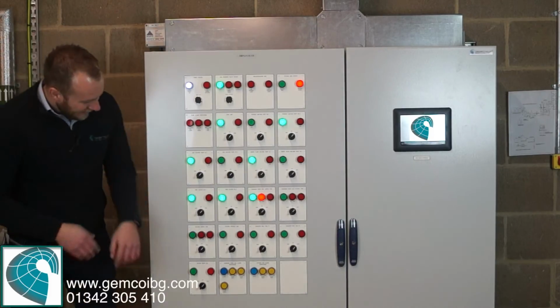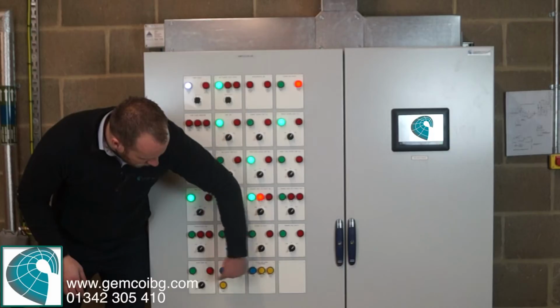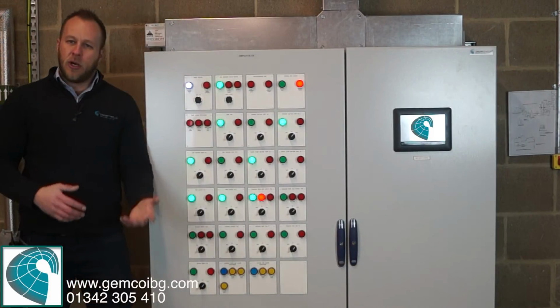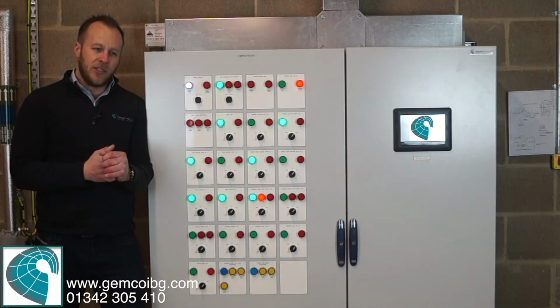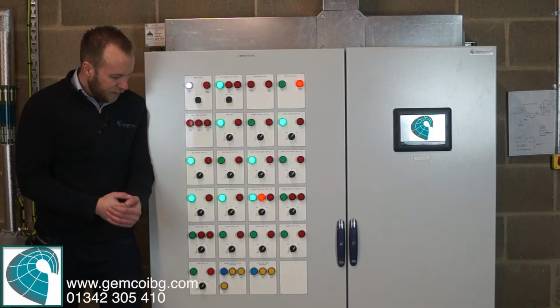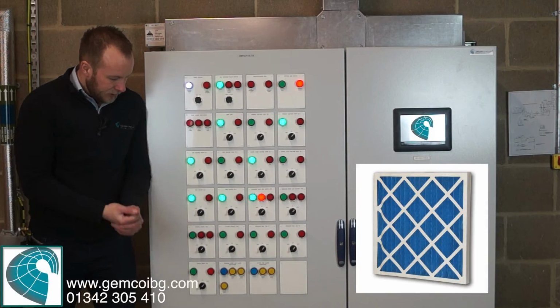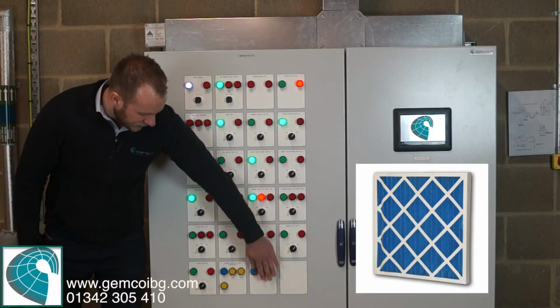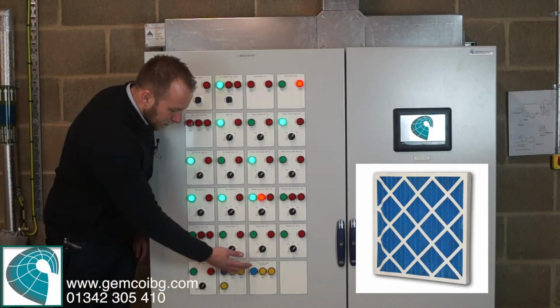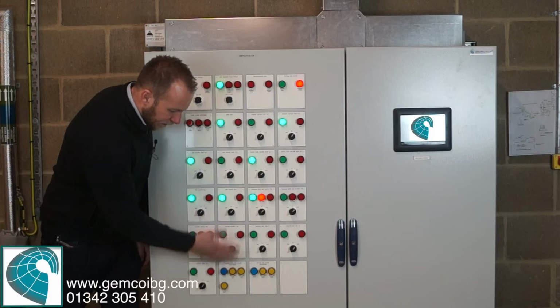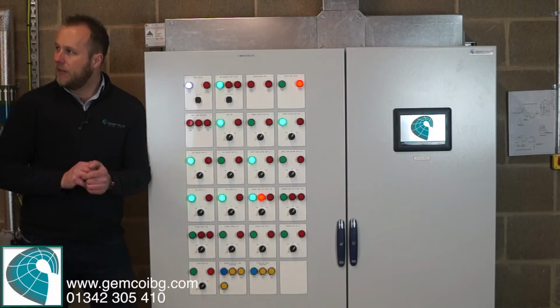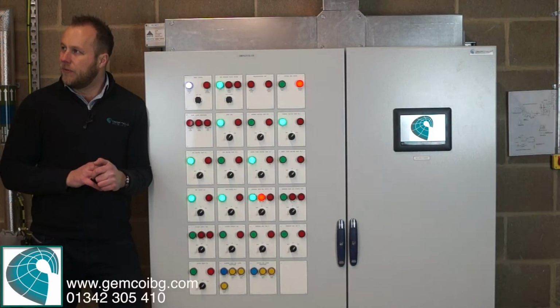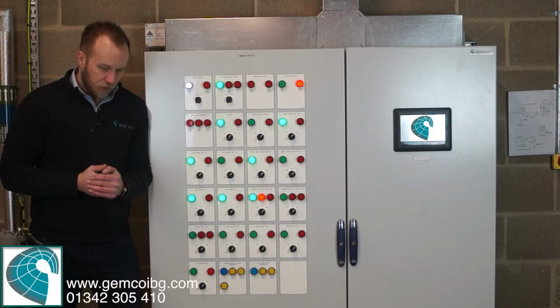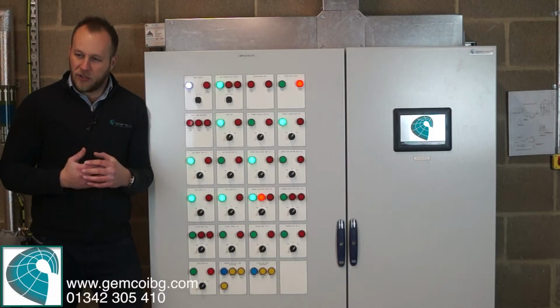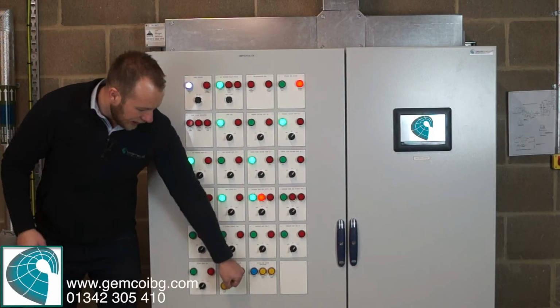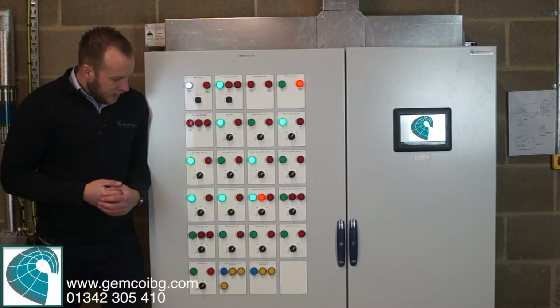All right, and then we monitor some filter alarms as well. So usually, if you've got planned preventative maintenance, you're changing the filters before they go off. But should you not, then they'll tell you when the filters are dirty on your air handling units. You may get some nuisance trips, they may come on and then go off. That means that they're just on the edge and they might need cleaning soon. So it's not rocket science. If you see that flicking on, soon you're going to have to change them, and if it's permanently on, then it's filthy.